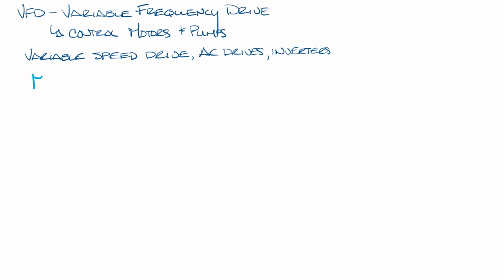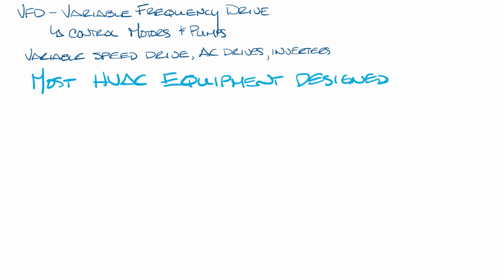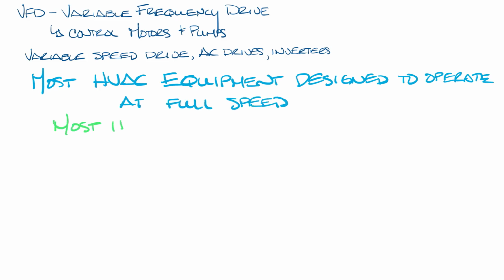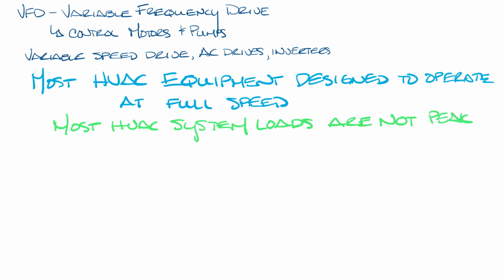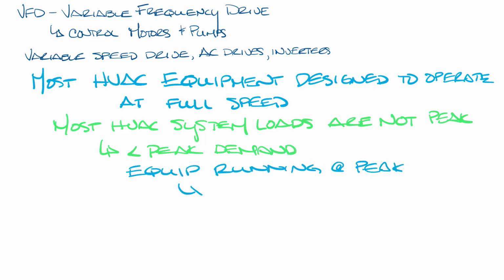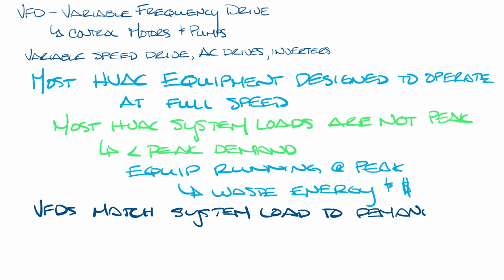VFDs are used because most conventional building HVAC system applications are designed to operate fans and pumps at a constant speed, but building loads are not constant. In fact, the majority of the time, buildings run below peak load. If during these times of less than peak demand, drive motors continue to operate at full speed, then they use the same amount of energy and will waste money, regardless of the actual heating and cooling load on the system. VFDs allow you to match the actual load throughout the year to save energy.